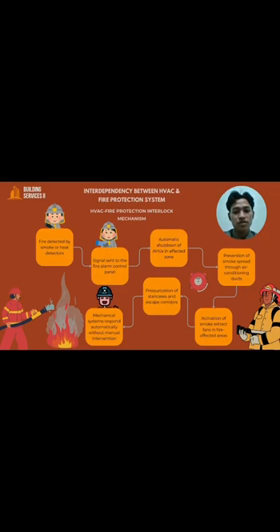Simultaneously, the system shifts into an active defense mode. We see the activation of smoke extract fans in the fire-affected areas to pull smoke out of the building. Finally, the system initiates the pressurization of staircases and escape corridors. By creating high pressure zones in these areas, we prevent smoke from entering the exit routes, providing a clear path for occupants to evacuate safely.